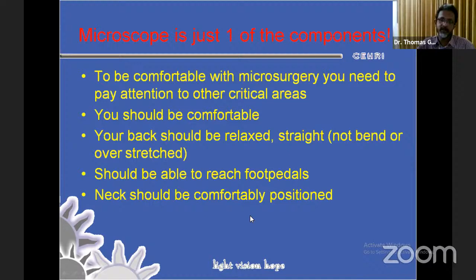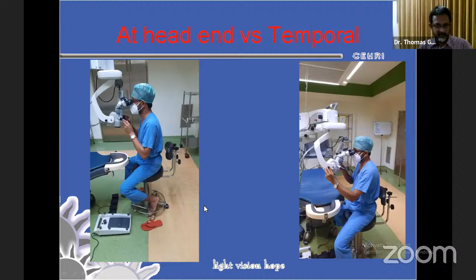So when you're sitting at the head under a microscope, you're much closer to the head of the patient, and your microscope is practically straight down like this. But if you're operating on the temporal side, as we do for our temporal phaco, typically temporal now, you need to tilt the microscope so that your back is still straight. If I had this position here, my head would be somewhere here, which means I'll have to have a bend like this, and at the end of the surgery, I'll have difficulty getting up again from the chair because my back is in spasm. So you need to tilt the microscope when needed, as and when required. All these adjustments need to be done. The foot pedal switches can be configured differently. This is not a pre-configured thing.